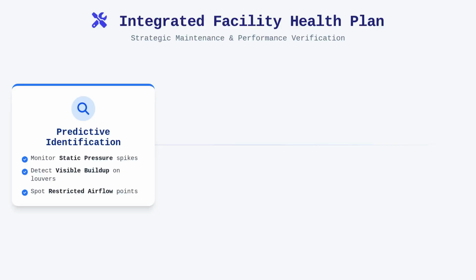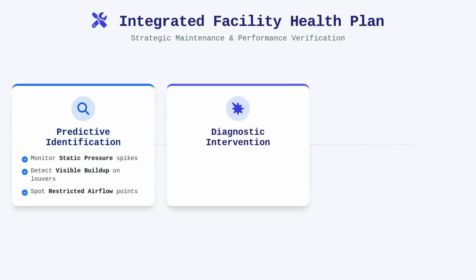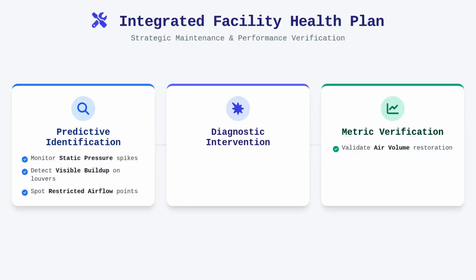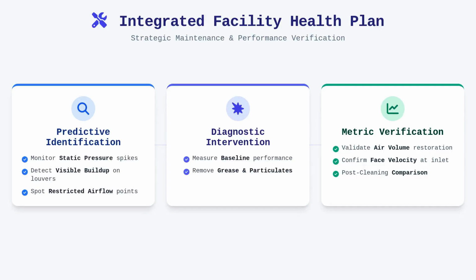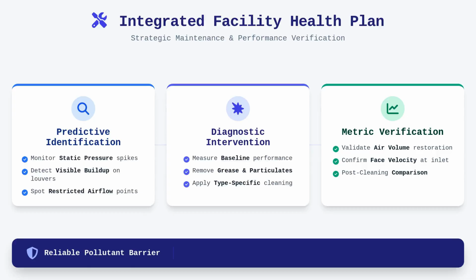Remember that the cleaning outcome is verified not just by visual inspection, but by the restoration of system performance metrics like air volume and face velocity at the inlet. This requires a diagnostic mindset where you measure the system before and after your intervention. By systematically addressing the risks of particulate accumulation and grease buildup, you ensure that the exhaust system continues to act as a reliable barrier against indoor pollutants and fire hazards.